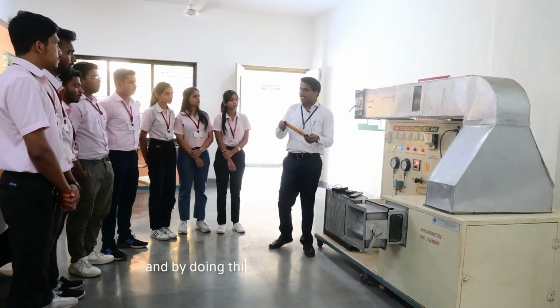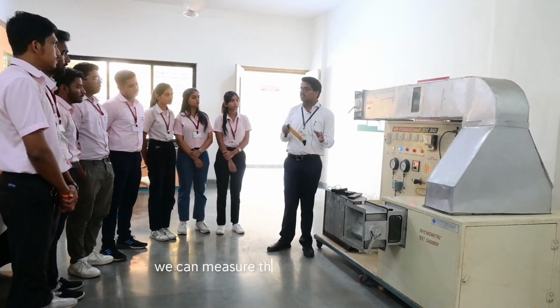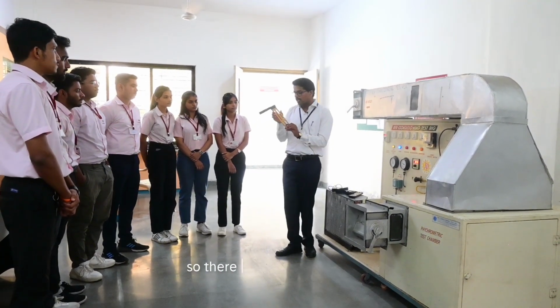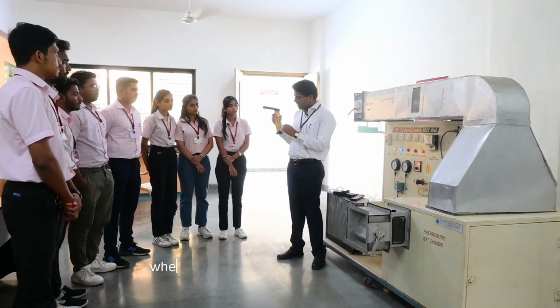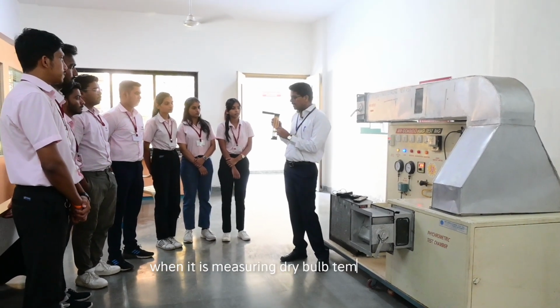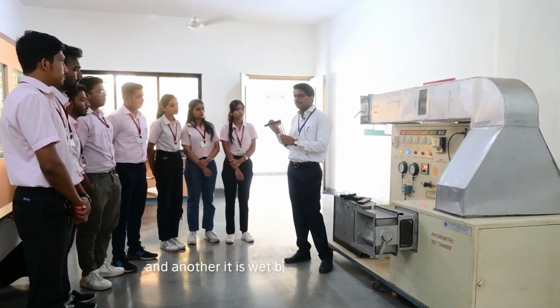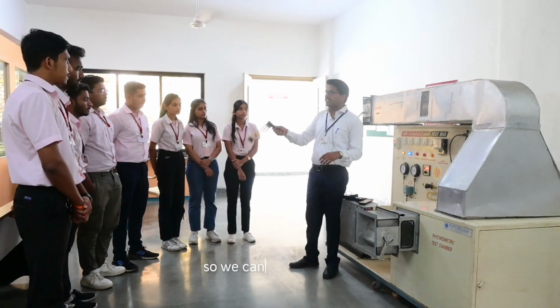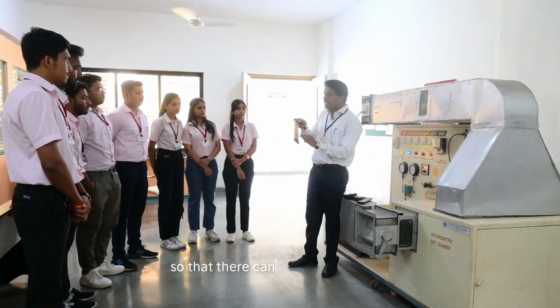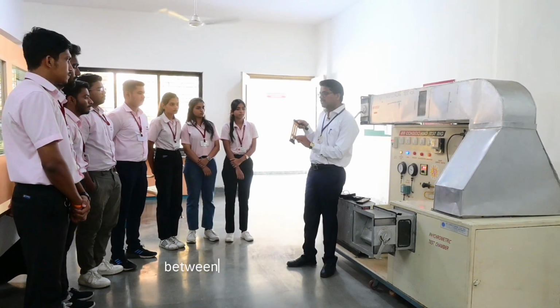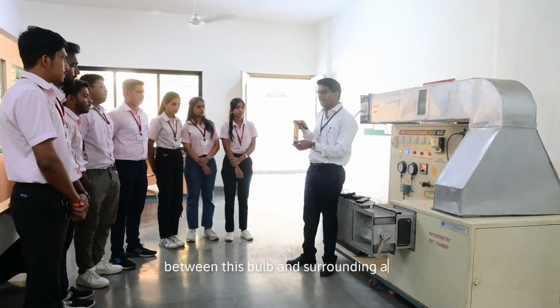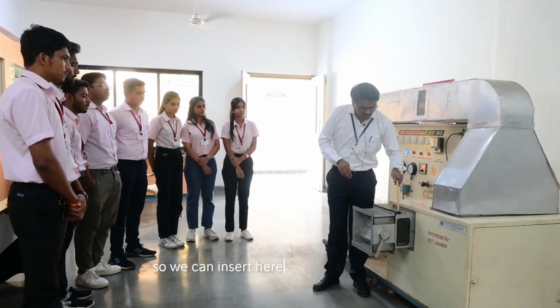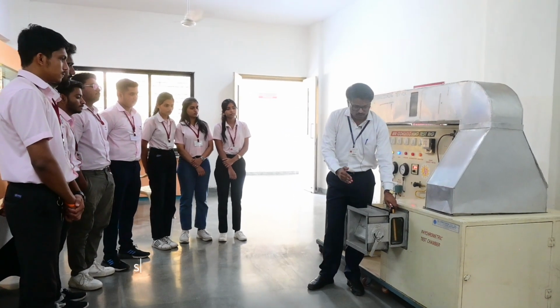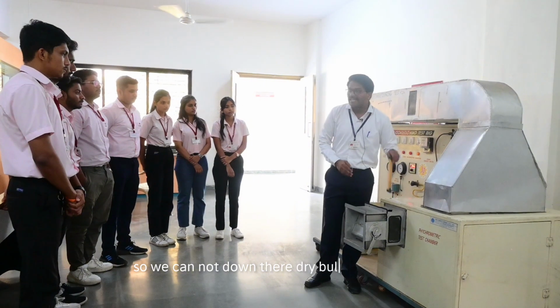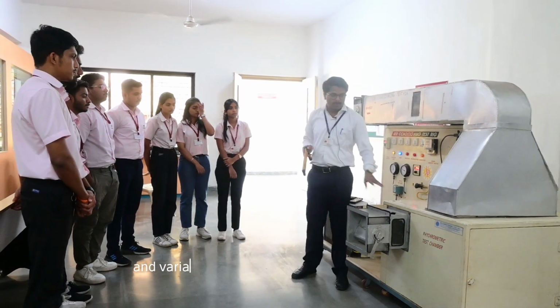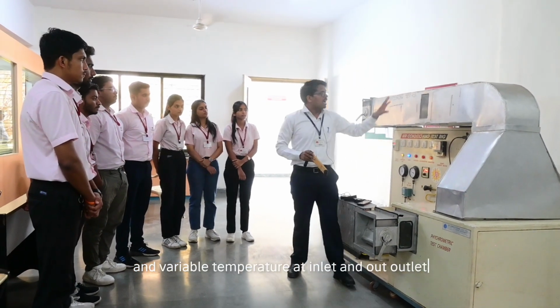And by using this sling type of psychrometer we can measure the condition of that air. So there are two thermometers. One is measuring dry bulb temperature and another is wet bulb temperature. Okay, so we can rotate it like this so that there can be relative motion between the bulb and the surrounding air. So we can insert it here. So this air is moving. So we can note down the dry bulb temperature and wet bulb temperature at inlet and outlet.